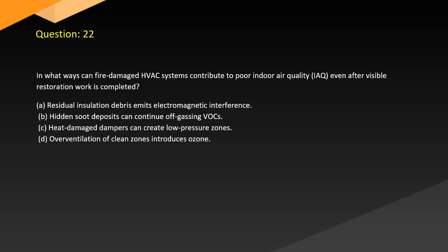Question 22. In what ways can fire-damaged HVAC systems contribute to poor indoor air quality, even after visible restoration work is completed? A. Residual insulation debris emits electromagnetic interference. B. Hidden soot deposits can continue off-gassing VOCs. C. Heat-damaged dampers can create low-pressure zones. D. Overventilation of clean zones introduces ozone.